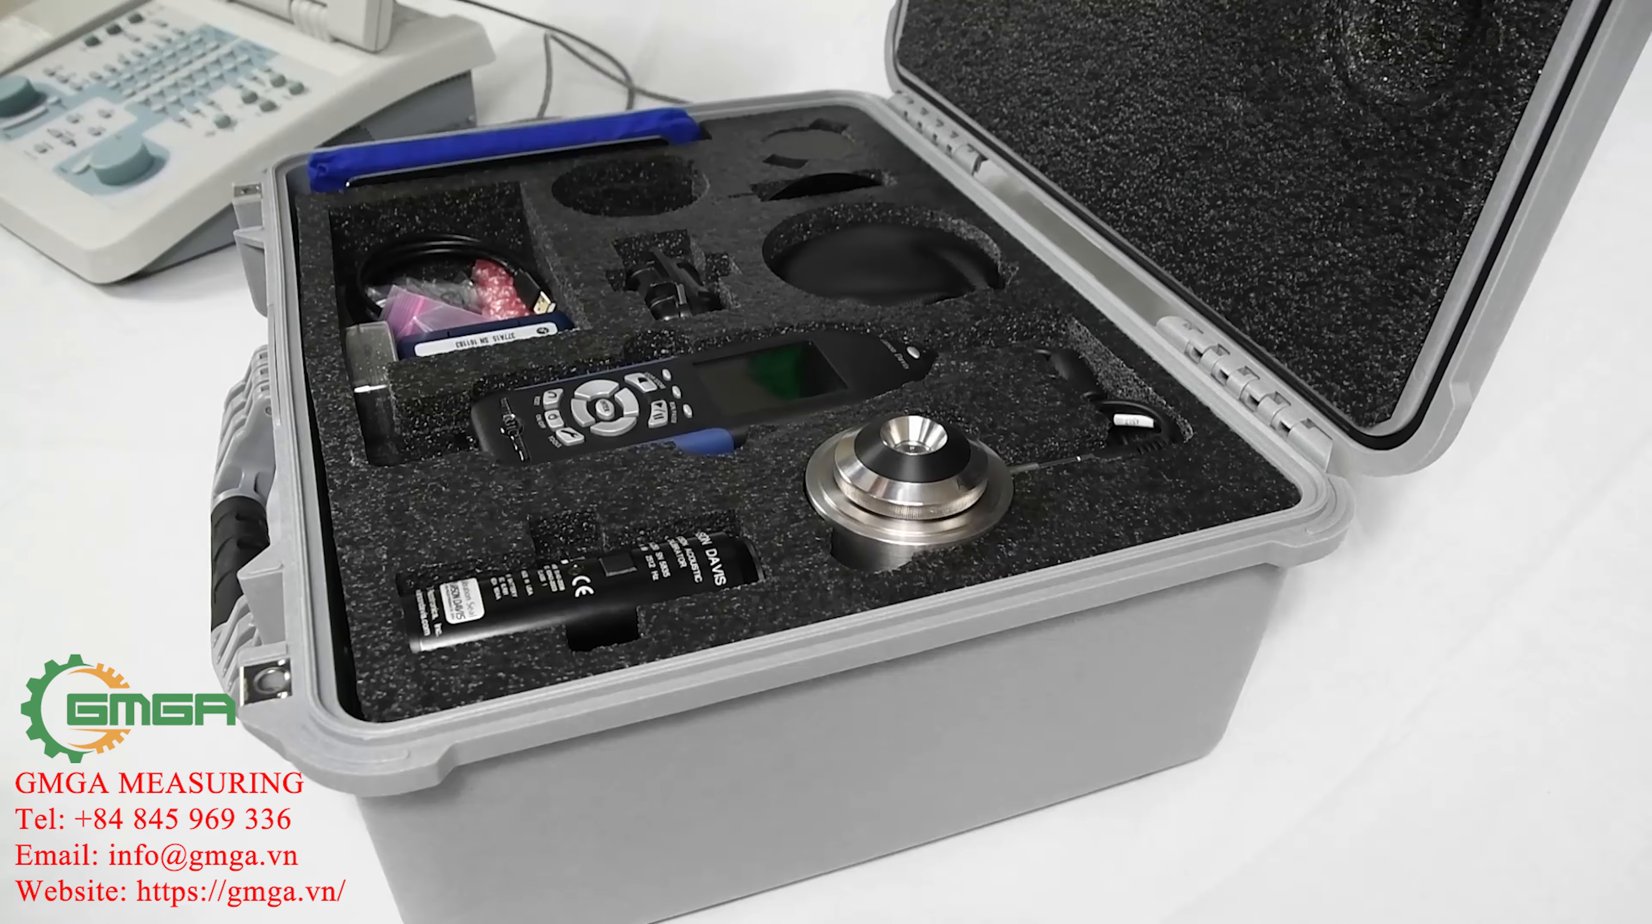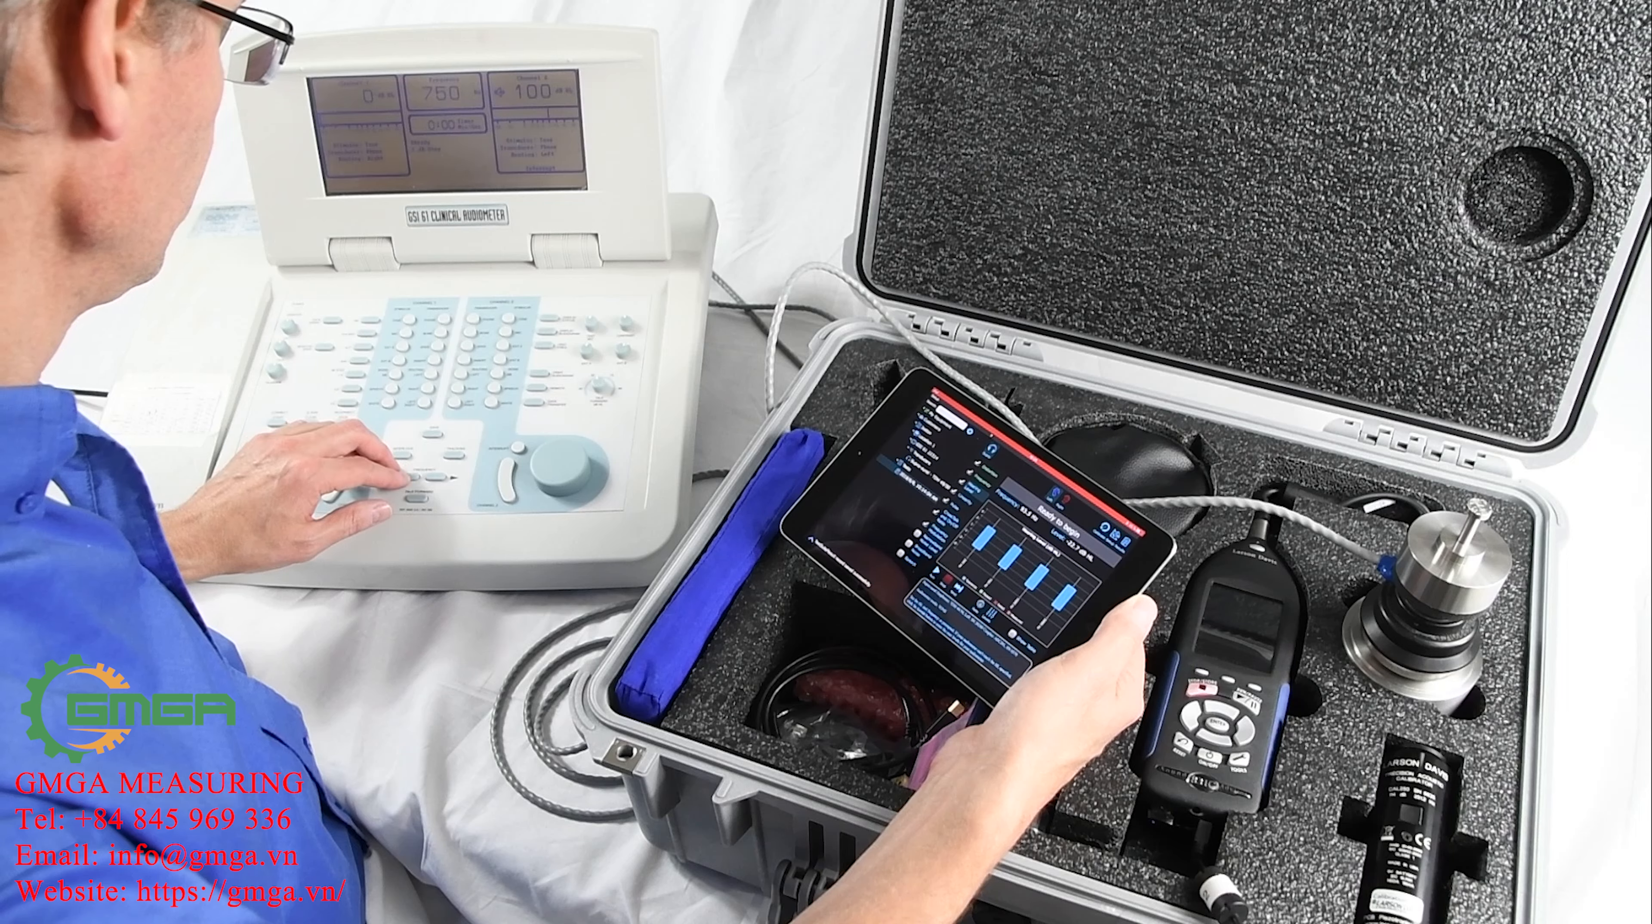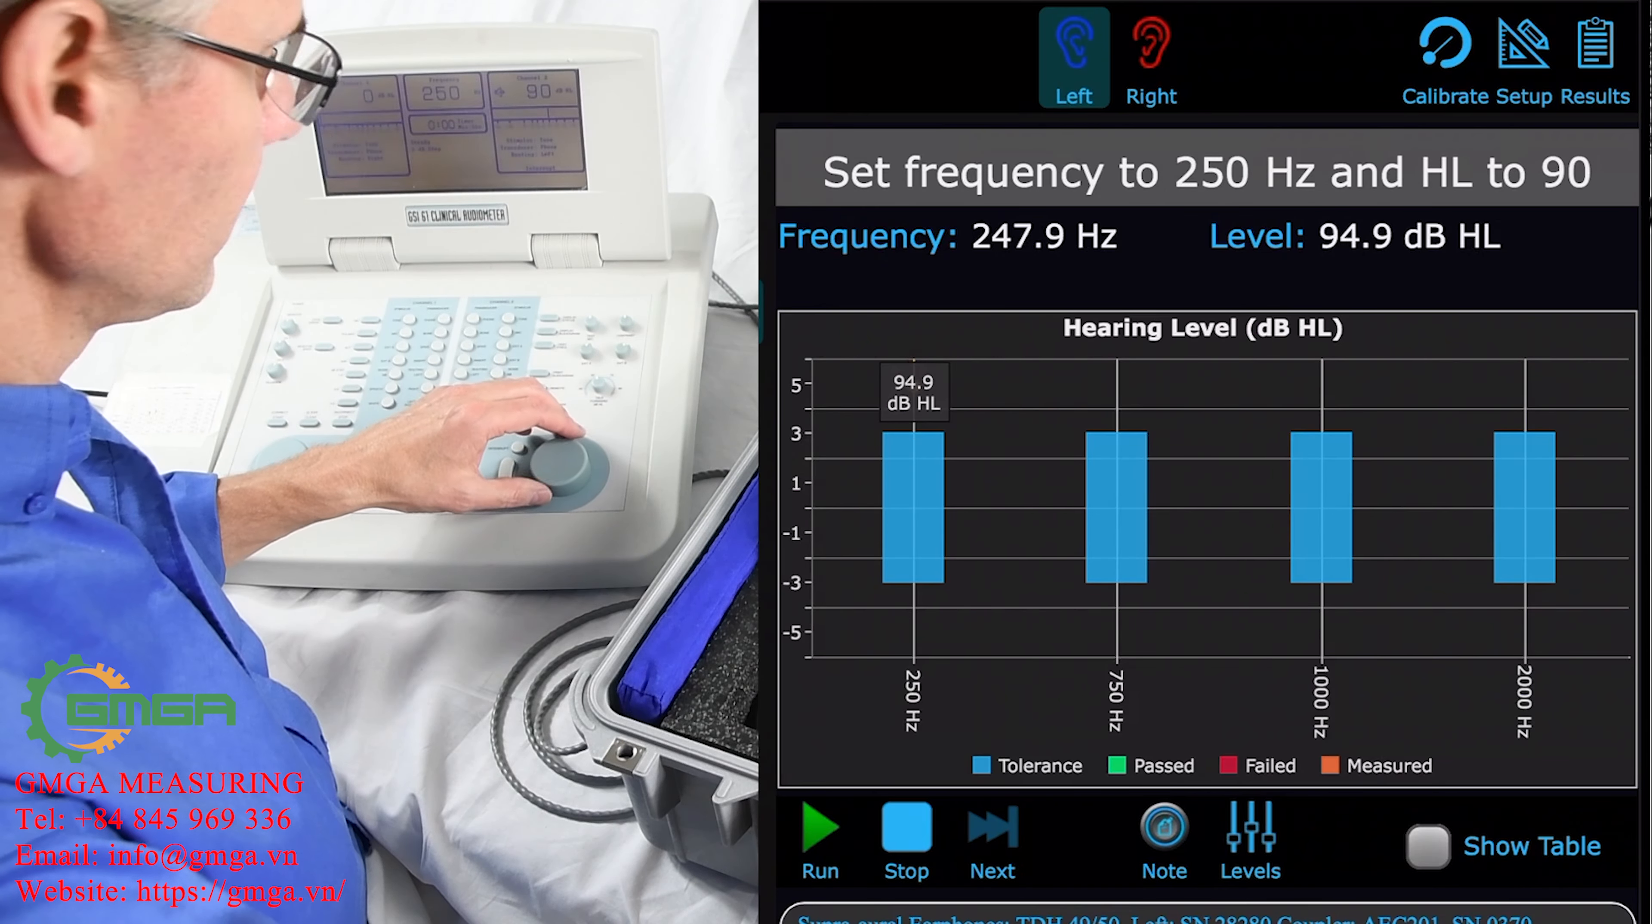AudCal is a system for testing audiometers. The Sound Advisor Model 831C sound level meter measures the frequency and DBHL from the audiometer.